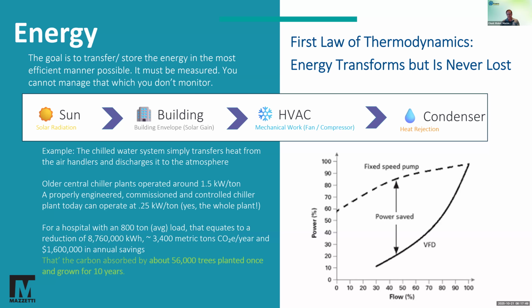I'm just going to do a quick plug here for the power curve for a VFD, and then I'll turn it over to Jim, who's going to tell us more about energy. This is the graph for a fixed speed pump: at 0% load, it's still 60% power, and the curve goes like this from flow to power. With a VFD, your curve starts down at about 10% power with 30% flow, and then also caps out at 100. I want to talk about this intersection here.